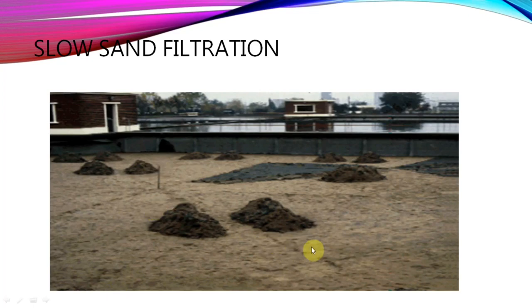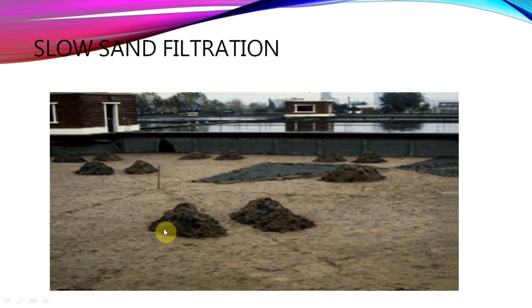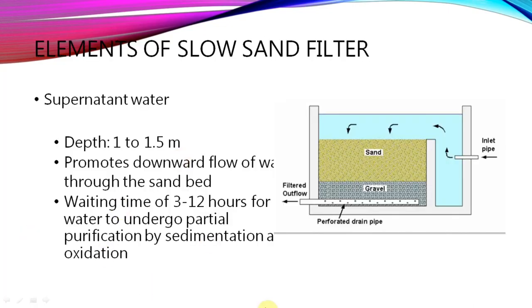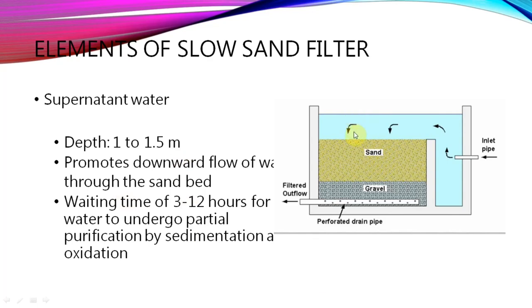After a period of time, the entire plant loses efficiency. What we see as heaps of sand are the top layers of unused plants. We scrape off the top biological layer and remove it. After a few weeks it has to be replaced. We drain the water, remove the old sand, add new sand, and wait for the top layer to become a biological layer again - it forms by growing algae and plankton over the sand surface. The supernatant water layer is 1 to 1.5 meters.